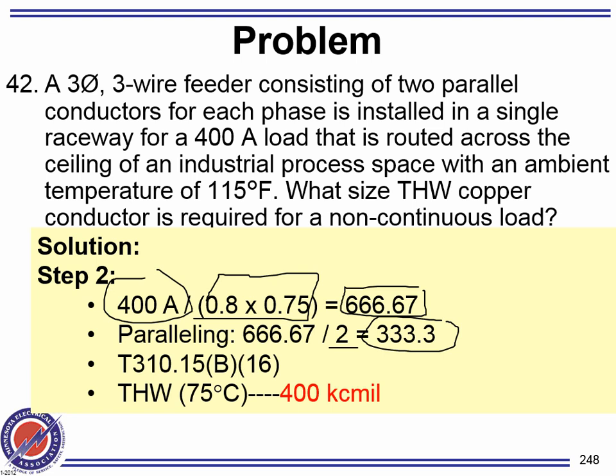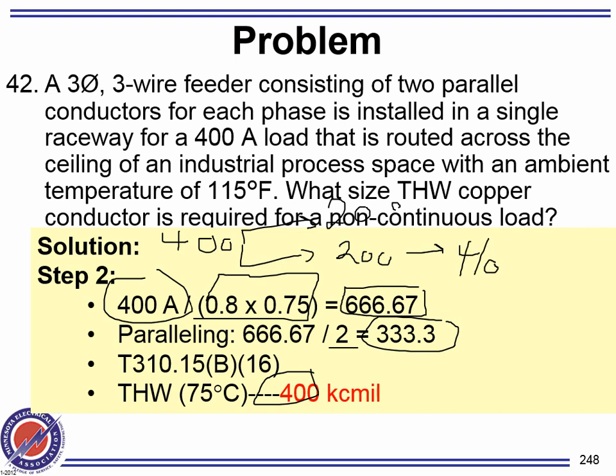And I'll get you number 4. Now do me a favor. Let's just see what the size would be if there was no derating. Now remember, you need to cut it into 2, so that'll be 200 amp. Everybody knows why? Because we're paralleling 2 sets. So we have 2 sets, 200 amp. Is there a 4 aught? I think it's 4 aught. Is it 4 or 3? 3 aught? Okay. 3 aught. You guys see the gravity? We went from 3 aught into how much? 400 kcmil because of bundling.